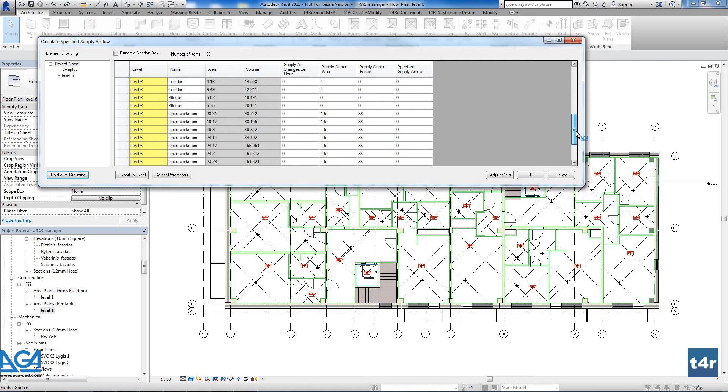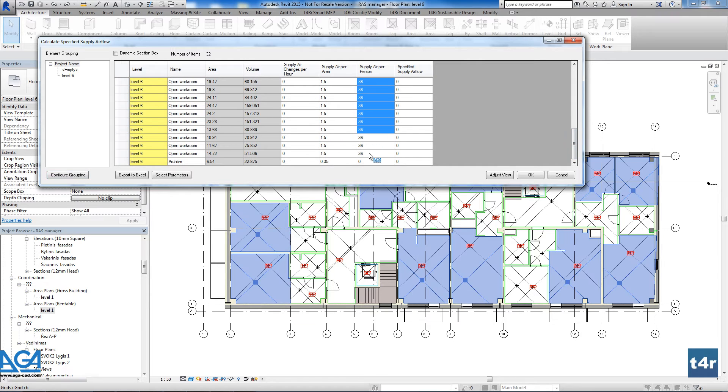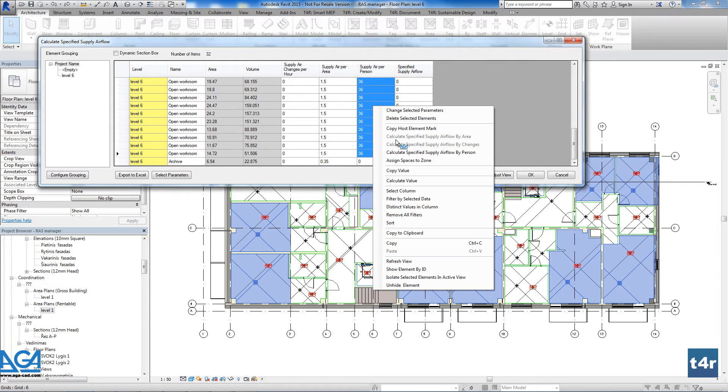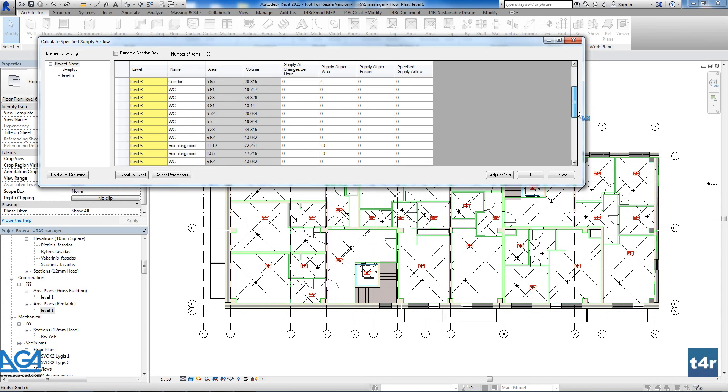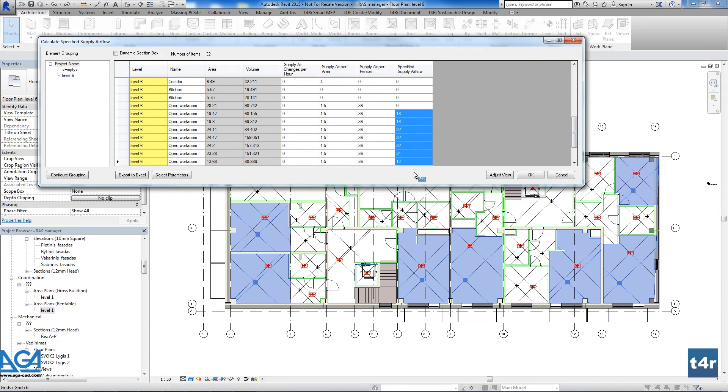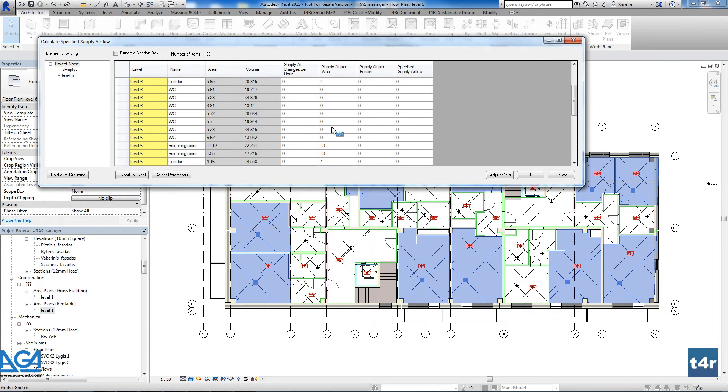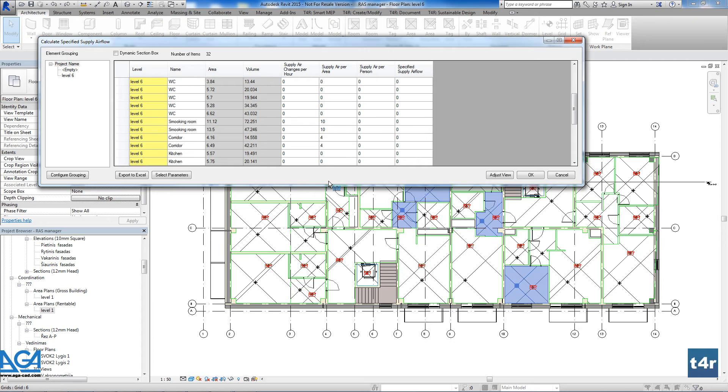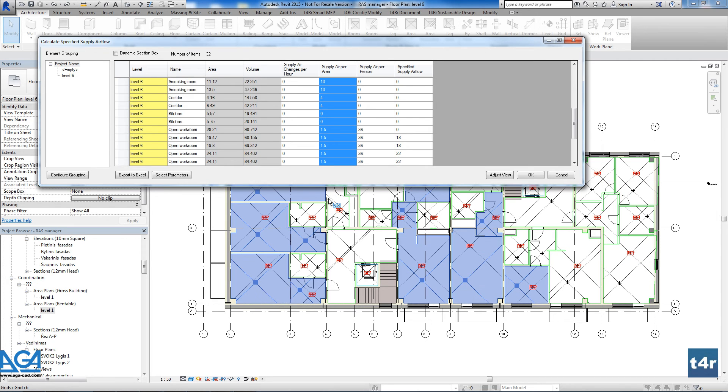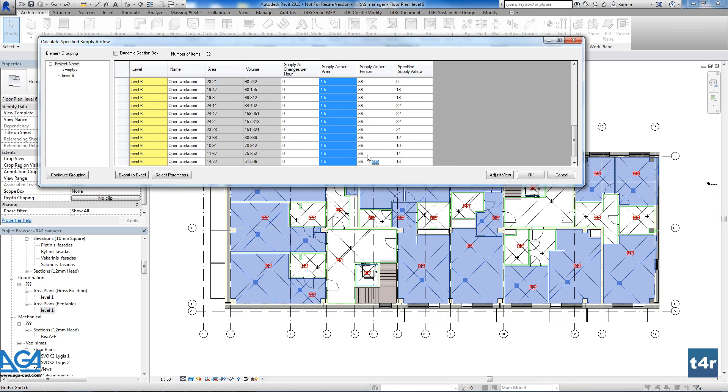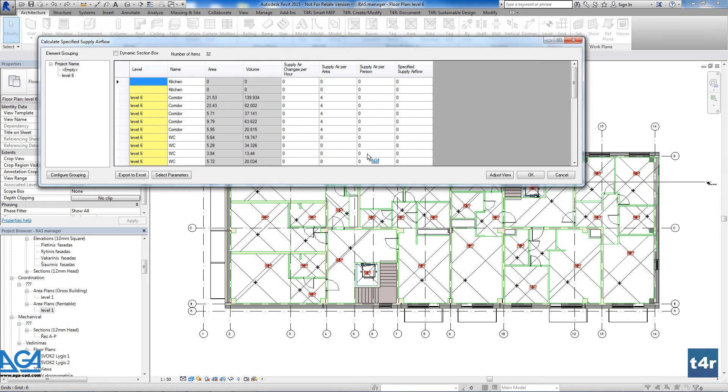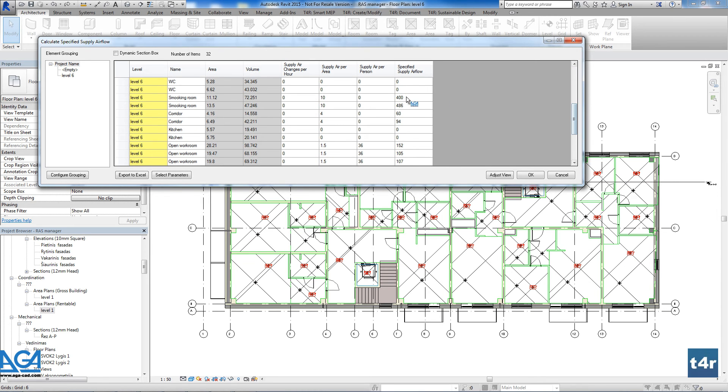For each space, we can adapt the special HVAC data according to which the supply and exhaust air will be calculated. All the data is taken from national standards and can be adapted to all countries. The solution can calculate the supply and exhaust air per area, per person, or by air change in the space.